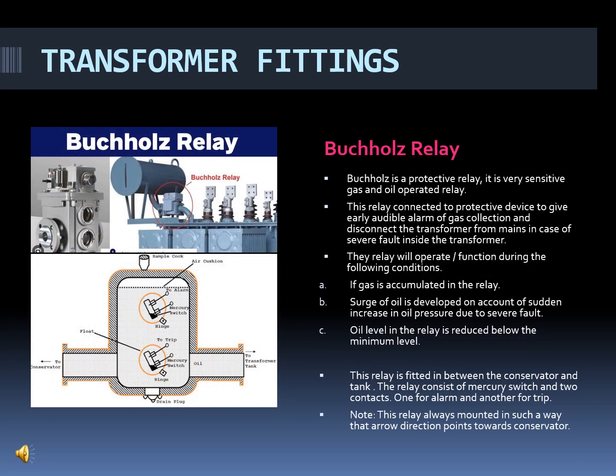Now the topic is Buchholz relay. The Buchholz relay is a very protective and very sensitive relay, and it is operated by gas and oil. The relay is connected to a protective device to give an early audible alarm for gas collection and to disconnect the transformer from the main supply in case of severe fault inside the transformer.